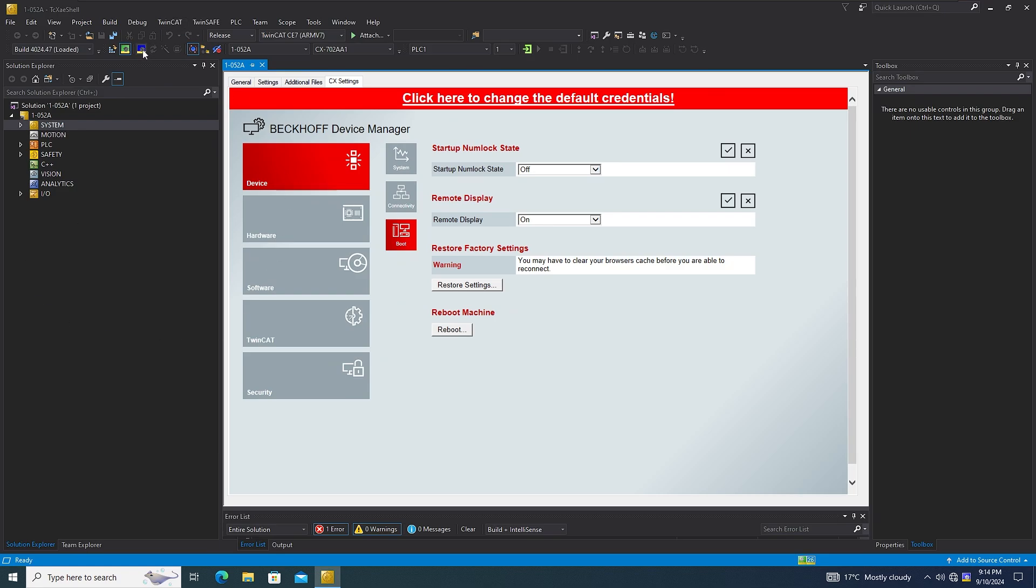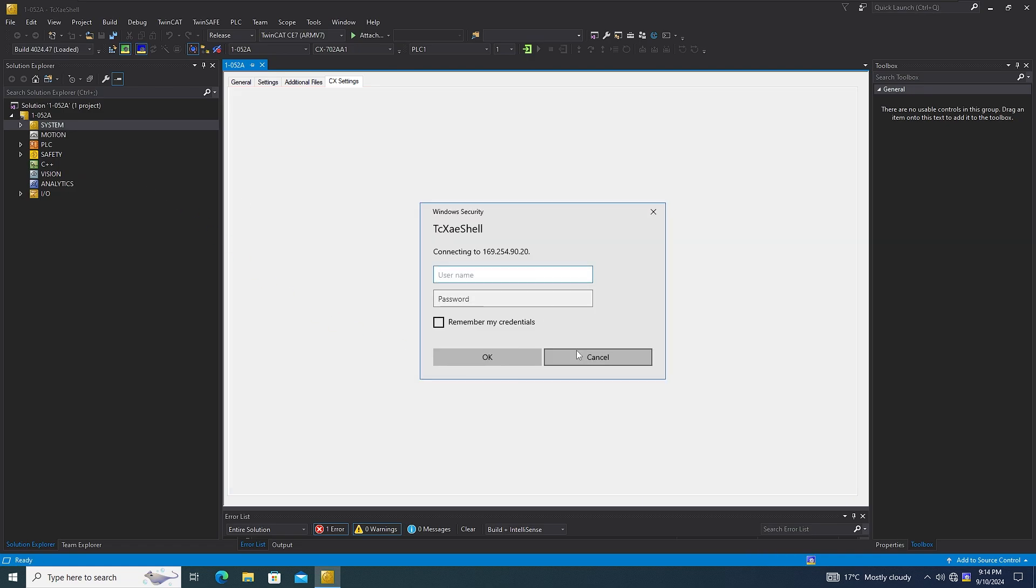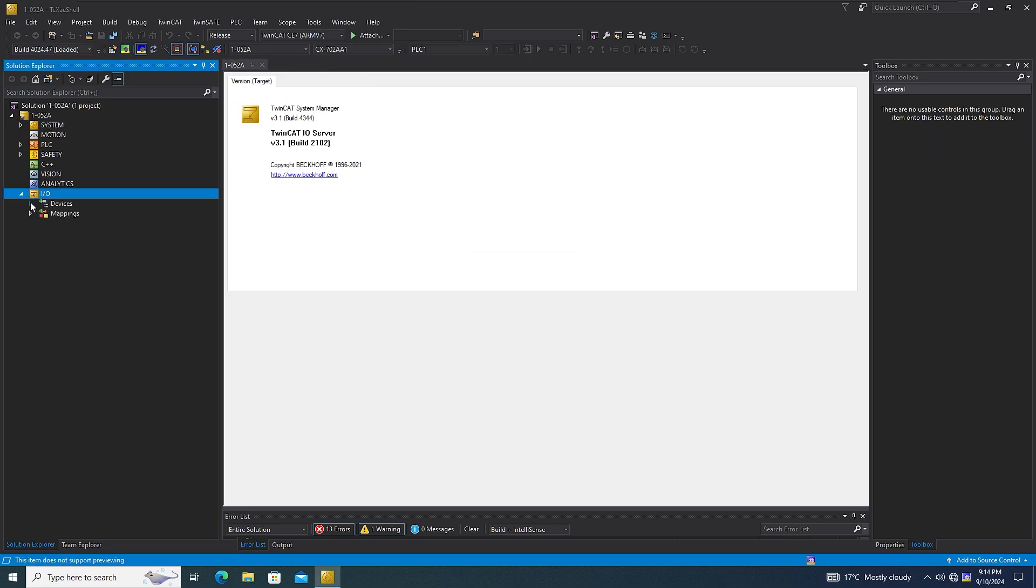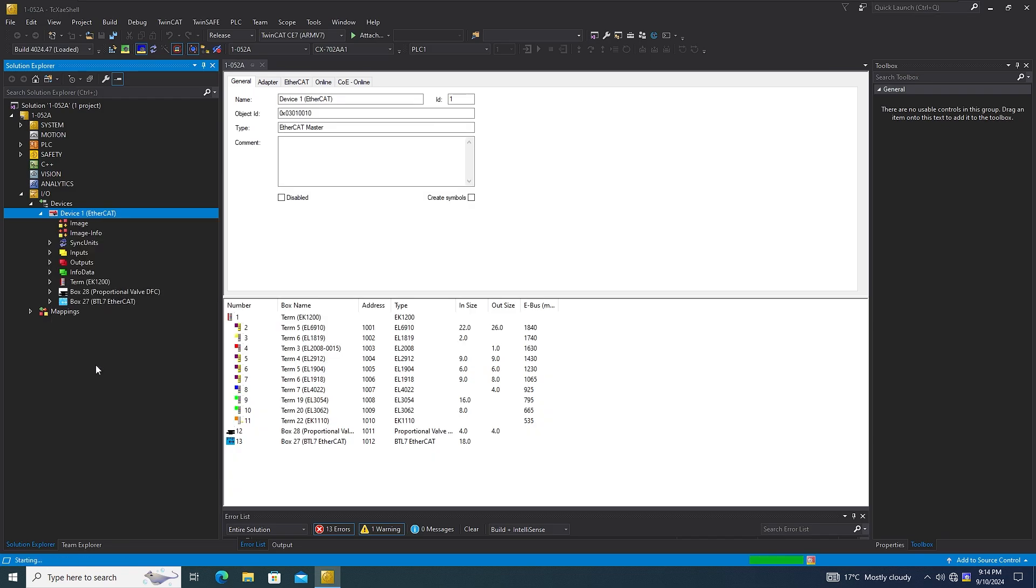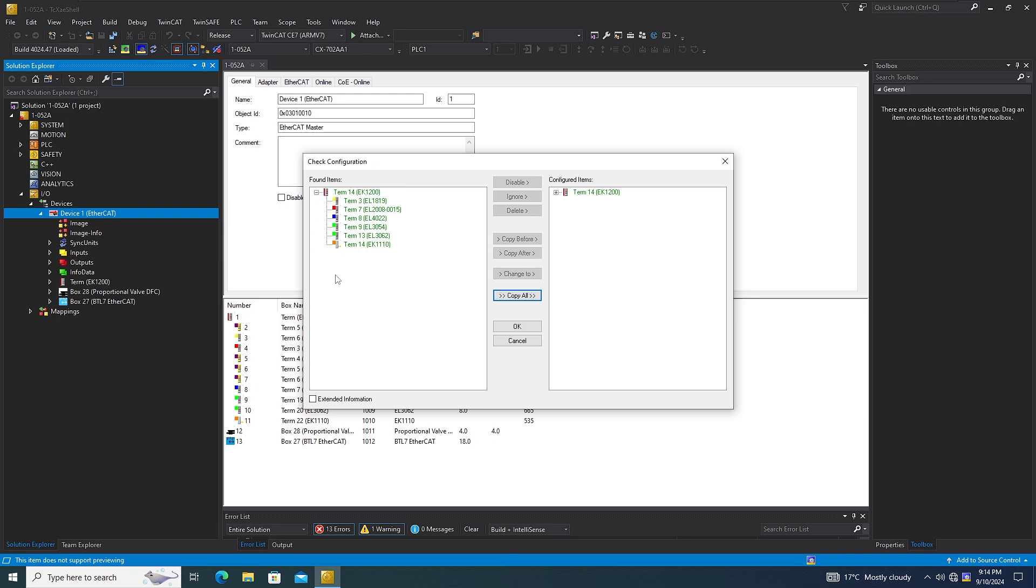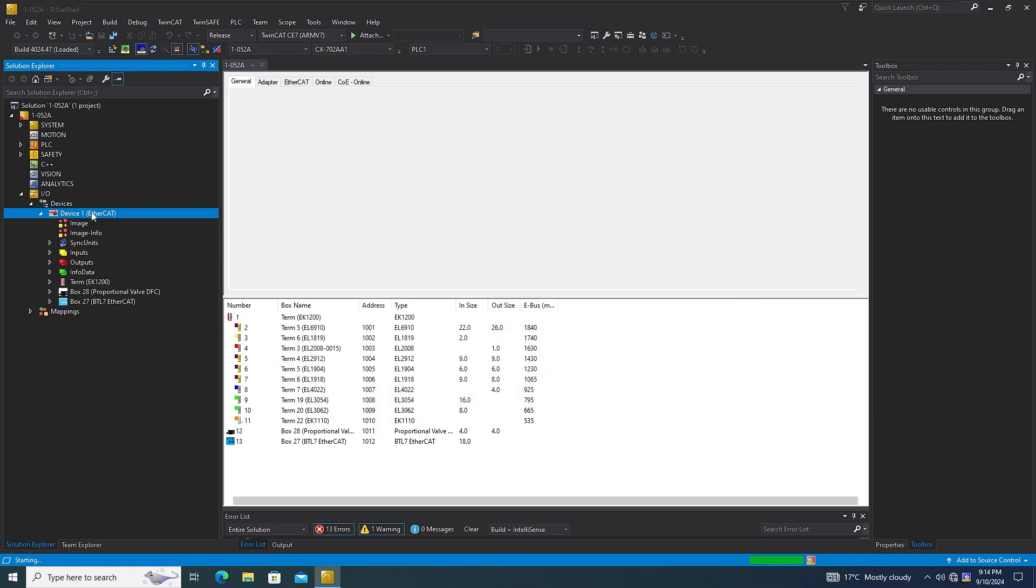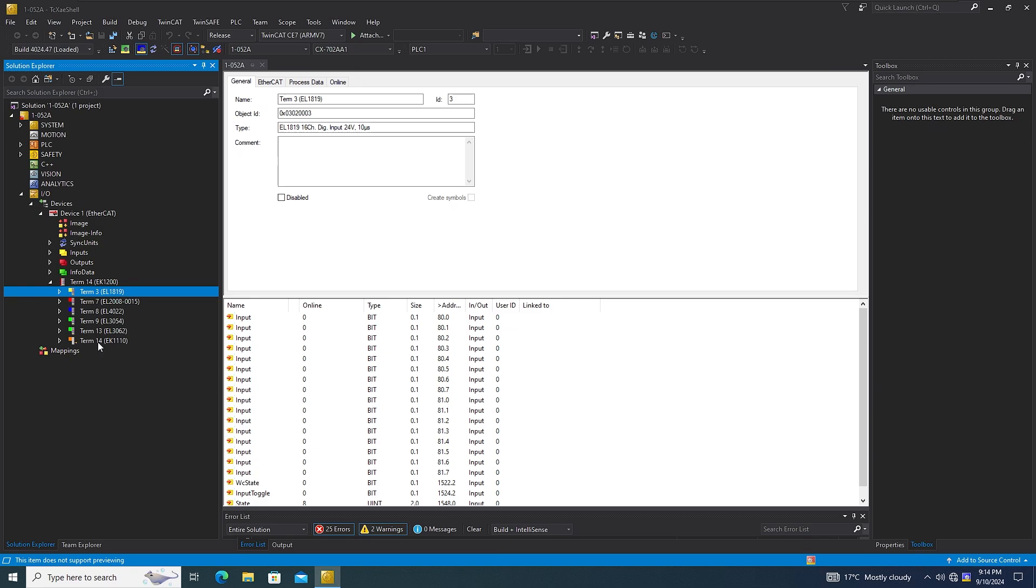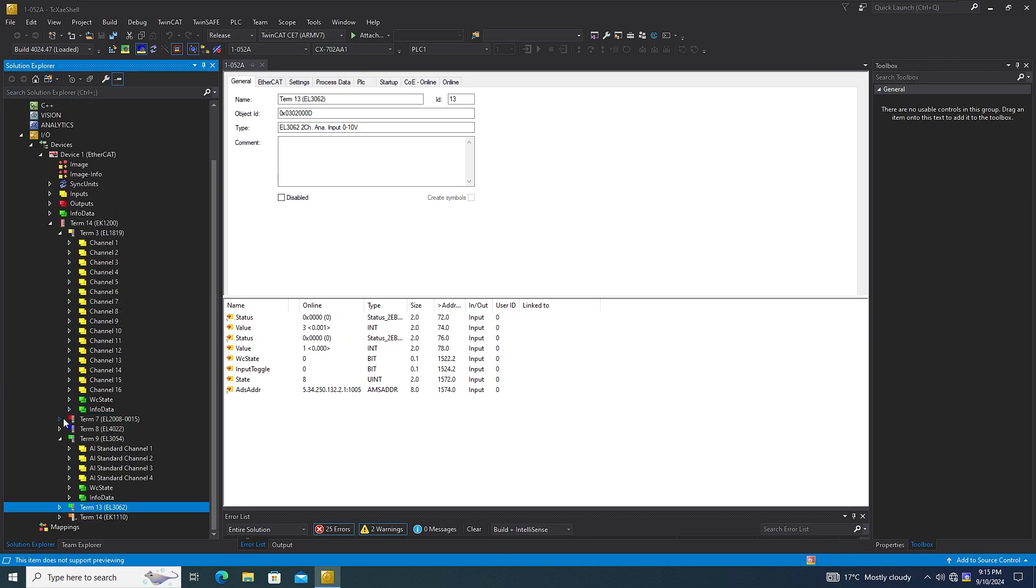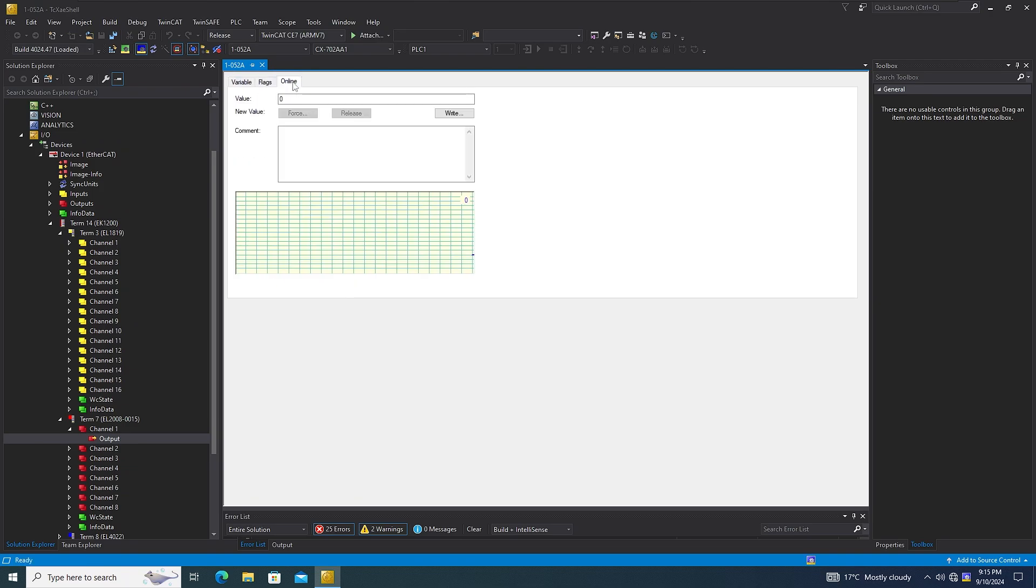You can go to config mode. In here you can scan the boxes, whatever is connected. Copy all. So whatever I got connected to the PLC, I'm going to see everything here. These are the cards that are connected to the PLC that I have. For example, this is an output card and I can see the online status of it as well.